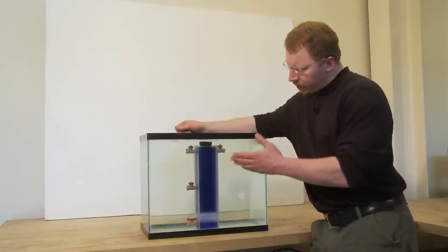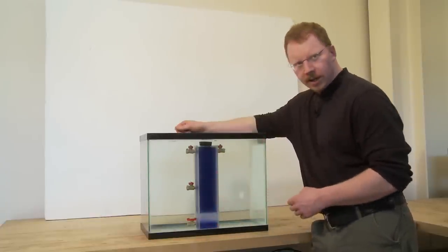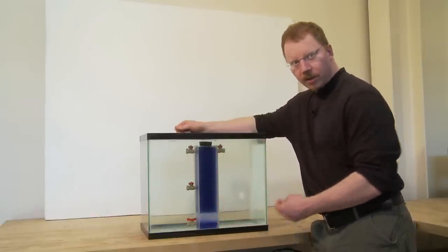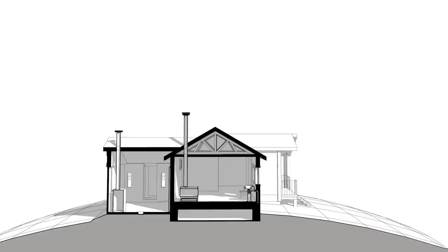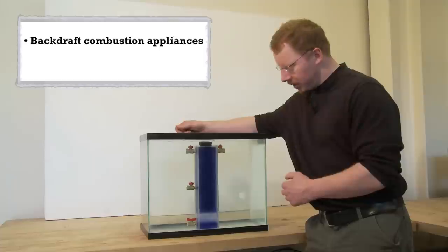If you have too much air leakage out of the top and you can't draw enough replacement air in from down low through leakage and holes, it may come in through a malfunctioning combustion appliance such as a boiler or a wood stove. Sometimes the stack effect will be powerful enough that it will actually pull wood smoke or combustion gas from a boiler into the house.